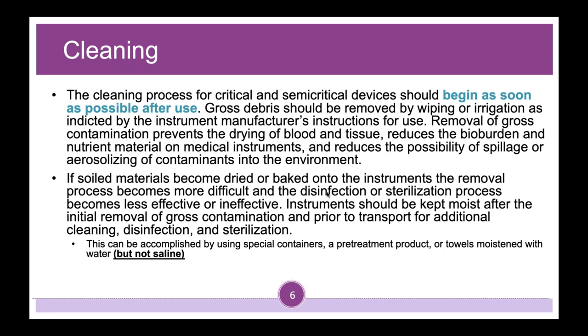If soiled materials become dried or baked onto the instruments, the removal process becomes more difficult and the disinfection or sterilization process becomes less effective or ineffective. Instruments should be kept moist after the initial removal of gross contamination and prior to transport for additional cleaning, disinfection, and sterilization.